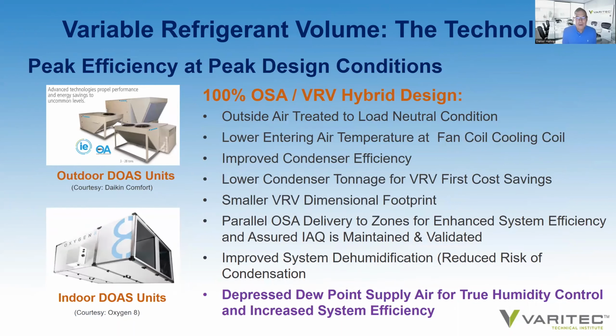So looking at 100% outside air VRV hybrid design, outside air is independently treated at the DOAS unit to a load neutral dehumidified condition. Lower entering air temperature at fan coil cooling coils means that the VRV system sees a decreased load. Consequently, you have improved condenser efficiency. You can downsize the VRV condensers accordingly, offering not only more efficiency and lower first costs, you also have the advantage of lower dimensional footprints in these systems.